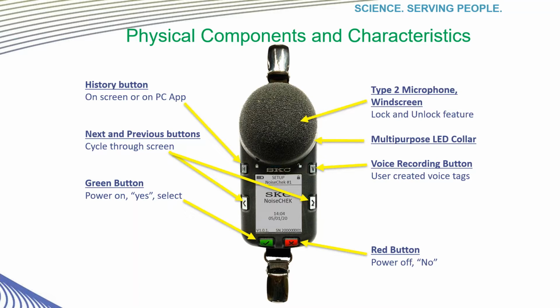The windscreen has an identifier that shows how to line up and lock it into place on the plastic clear ring. This ring also allows the user to see flashing LEDs that identify the status of the dosimeter from a distance. Two aggressive clothing clips assure a secure holding during the monitoring period.